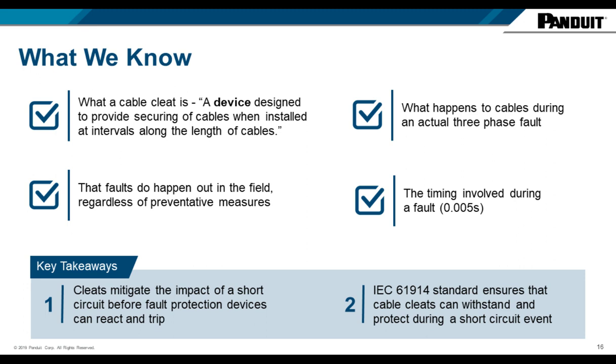To summarize: we now know what a cable cleat is — a device designed to secure cables. We understand what happens to cables during an actual fault, we acknowledge that faults do happen in the field, and we understand the timing involved — five milliseconds for the most destructive forces. The key takeaways: cleats do mitigate the impact of a short circuit before other fault protection can react and trip, and the standard IEC 61914 ensures that cable cleats can withstand and protect during that short circuit.